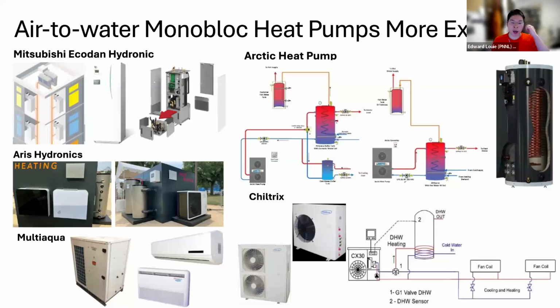These systems also, a heat exchanger is really important. We'll get more into that in subsequent slides, but on the right-hand side of the slide, you see a tank that has an internal heat exchanger, and that heat exchanger is pretty large. It runs pretty much the entire vertical height of the tank. The other one in the lower part of the slide, by Chiltrix, at least in the diagram, it shows that the heat exchanger area is only in the lower part of the tank.